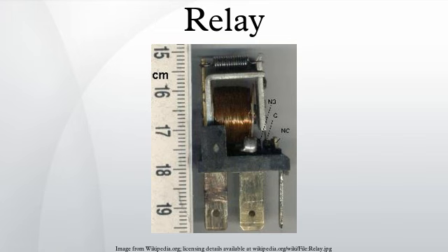In the two-coil example, a pulse to one coil turns the relay on and a pulse to the opposite coil turns the relay off. This type of relay has the advantage that one coil consumes power only for an instant, while it is being switched, and the relay contacts retain this setting across a power outage. A remnant core latching relay requires a current pulse of opposite polarity to make it change state. A stepping relay is a specialized kind of multi-way latching relay designed for early automatic telephone exchanges.